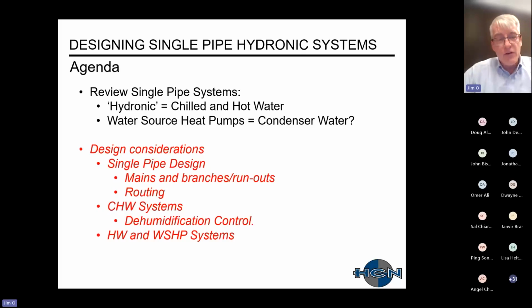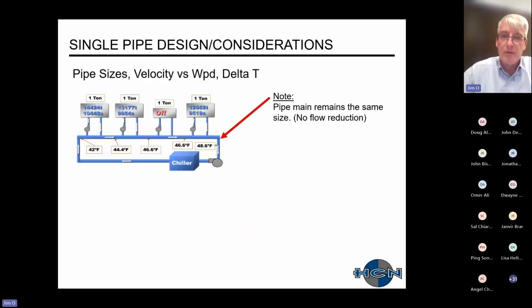All right, so let's talk a little bit more about design considerations with single pipe systems. I'll go over just the differences of how to work the mains and branches and runouts. I'll show a couple of examples of the routing. And then with chilled water systems, I want to highlight that you still have to be careful with dehumidification control. And then I'll go over quickly what the implementation is or things to watch out for with your hot water and water source heat pump systems.